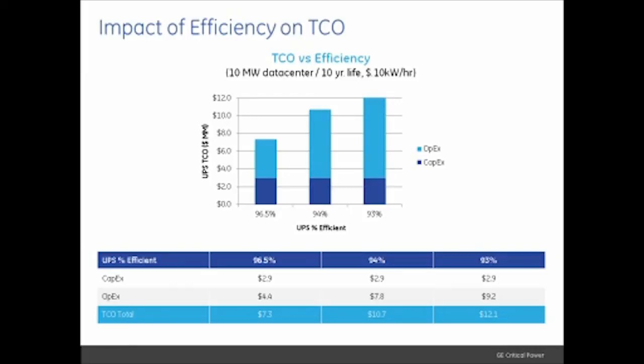Look at the difference in the overall 10-year TCO as you improve efficiency from 93% to 94%. That one step makes a difference of a little over $1 million, about $1.5 million over a 10-year period. If you go with some of the more efficient UPSs available today at 96.5% efficiency, and there are several out there with that efficiency, it drops the TCO from 12.1 to just about 7.3. A huge drop, so it does make a very large difference overall.